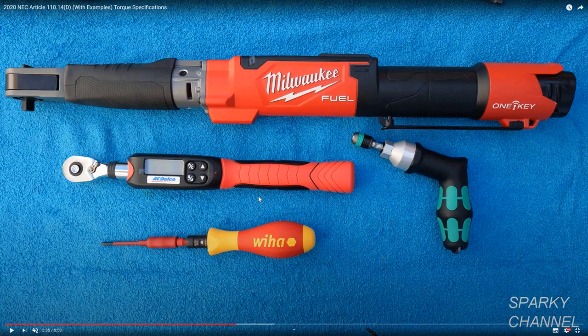Because when a stud breaks, that motor is no good until you repair it. That can be a very expensive cost, yeah? So cost of calibration and tool is less than a short and equipment failure. So if the motor fails because the stud was too tight and as it goes hot, cold, it breaks, that motor could be down for weeks. The use of a torque wrench guarantees that you don't go too tight or too loose. If it's too loose, you could have a line-to-line short. It could build up resistance, build up carbons, arcing, sparking. It could cause an explosion. If you don't properly torque your studs, terminations, terminals, you can cause a potential source of ignition. So to say that you can't use these because of cost, you're costing yourself lots of money.